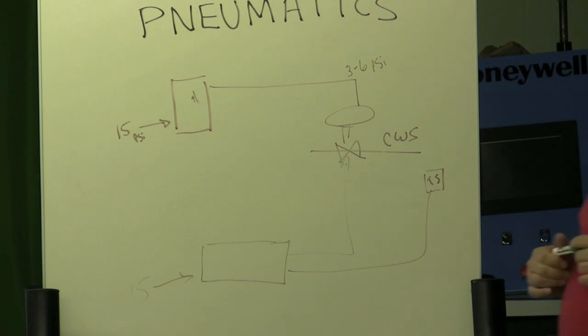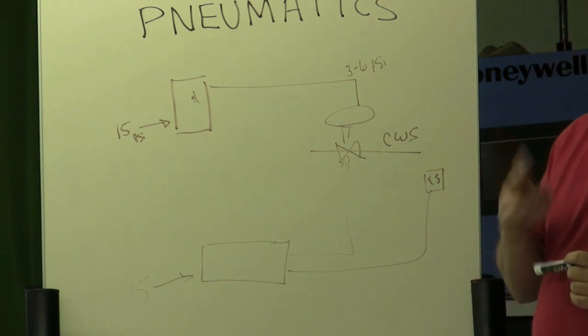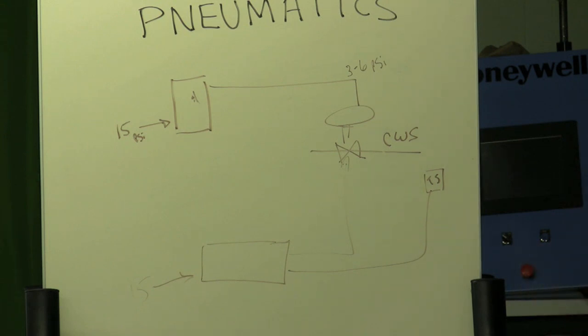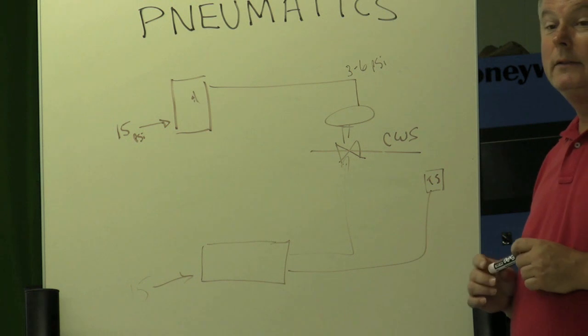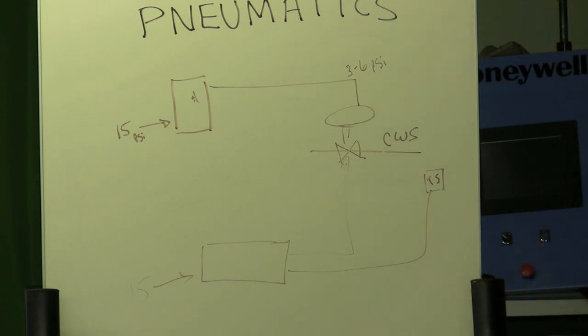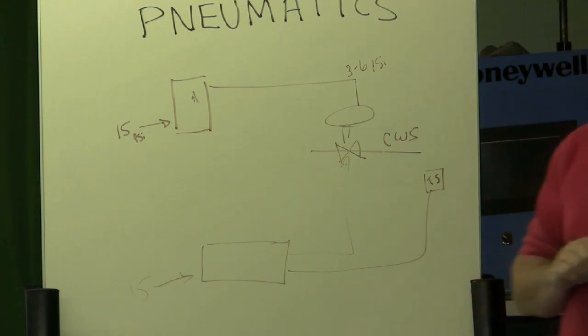Transmitters kind of work the same way. There are two-wire transmitters, and there are four-wire devices. A two-wire transmitter is what you're going to see most of the time. Any of those pressure transmitters that we have back there on the back row are two-wire devices.